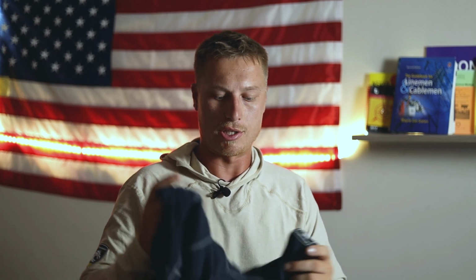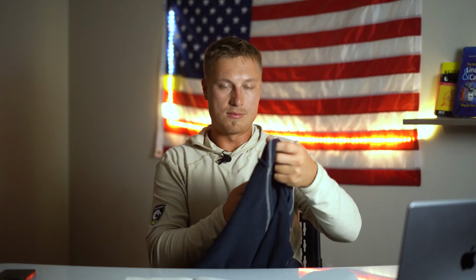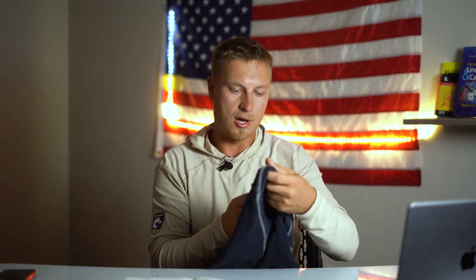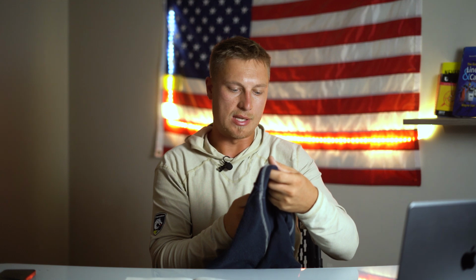And here I have a Dragon Wear hoodie that I got. This has a rating of Cat 3, which is a little bit thicker, and an arc rating of 28. So 28 calories per centimeter squared and a Cat 3, so it's a little bit more protection. Now, some places might require that. The sweatshirt is 48% modacrylic, 38% lyocell, 9% aramid, and 5% spandex. So it's a very comfortable sweatshirt. One of my favorites. I don't even wear it at work, honestly, because I like it so much. It's so comfortable and it looks really good.